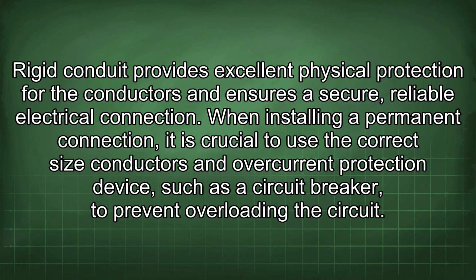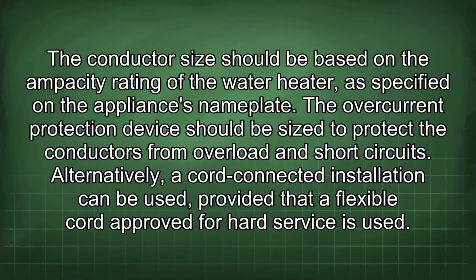Rigid conduit provides excellent physical protection for the conductors and ensures a secure, reliable electrical connection. When installing a permanent connection, it is crucial to use the correct size conductors and overcurrent protection device such as a circuit breaker to prevent overloading the circuit. The conductor size should be based on the ampacity rating of the water heater, as specified on the appliance's nameplate. The overcurrent protection device should be sized to protect the conductors from overload and short circuits.